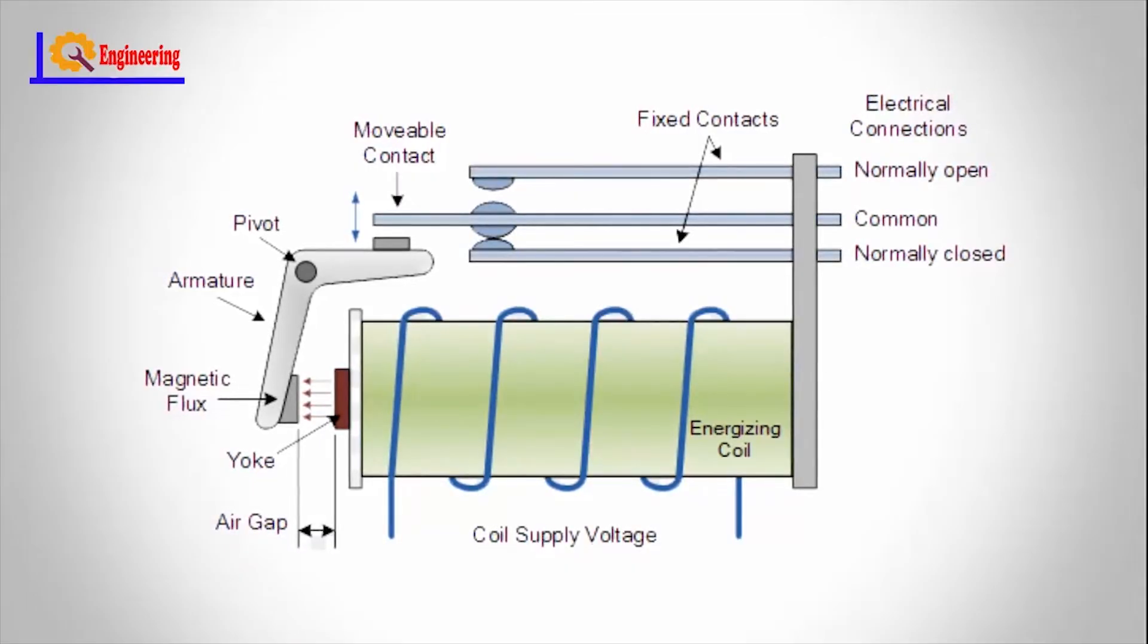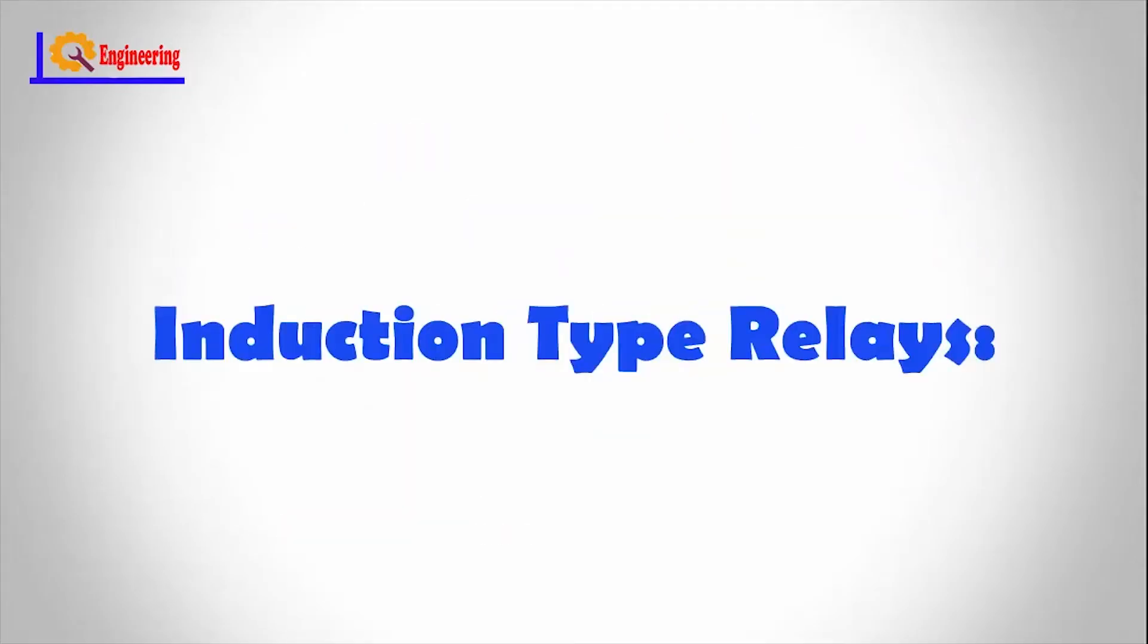Induction type relays: these are used as protective relays in AC systems alone and are not usable with DC systems. The actuating force for contact movement is developed by a moving conductor that may be a disc or a cup through the interaction of electromagnetic fluxes due to fault currents. These are of several types like shaded pole, watt-hour, and induction cup structures, and are mostly used as directional relays in power system protection and also for high-speed switching operation applications.